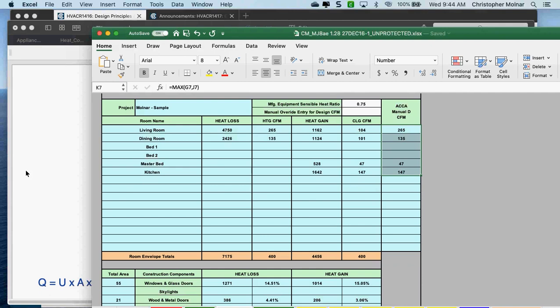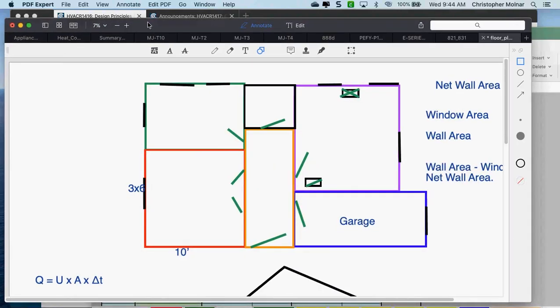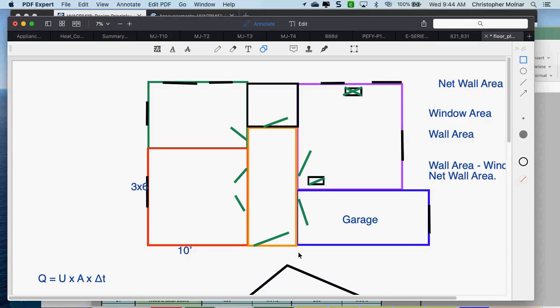No return grill in bathrooms or the kitchen — kitchen because of grease and cooking odors, bathroom because of odors. So you're going to lay out the supply and return.